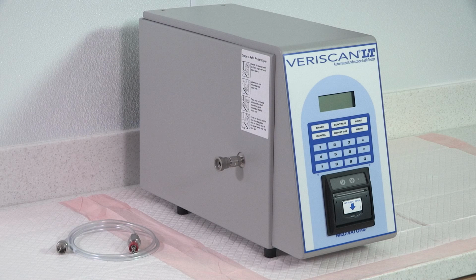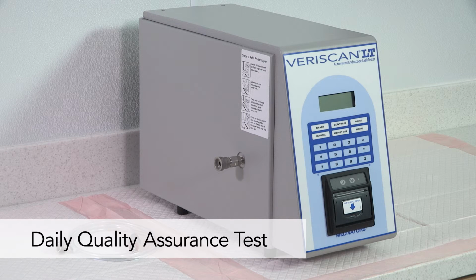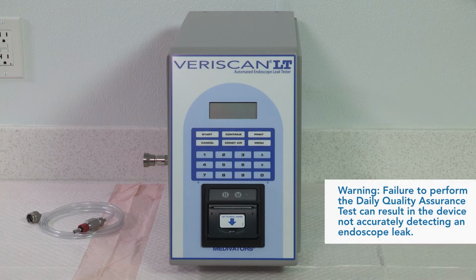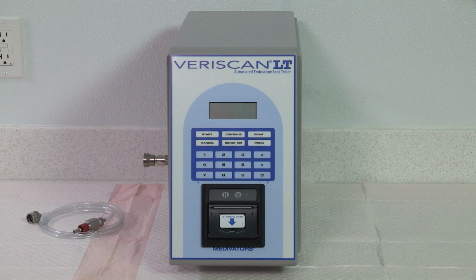Once the VERISCAN Leak Tester is set up, you're ready to continue. To verify the unit is operating properly, the daily QA test must be performed prior to the first use of the day. This test ensures the internal integrity of the VERISCAN Leak Tester and its ability to properly sense an endoscope leak. Failure to perform the daily quality assurance test can result in the device not accurately detecting an endoscope leak. Only use the VERISCAN Leak Tester if the daily QA test was successfully performed and a pass result is received.